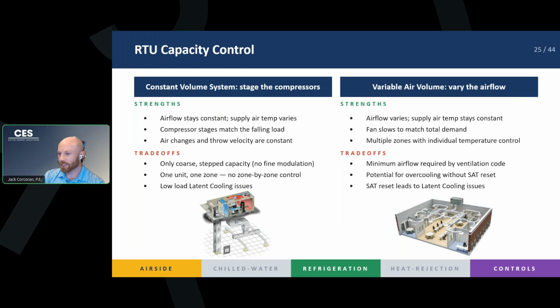The drawbacks of this is that, I will say many modern rooftop units can use variable speed compressors that can modulate just like VRF, and those are very powerful, but they add to the cost, and maybe you don't need it. So the simple rooftop configuration, constant volume with staged compressors, has some trade-offs that you can imagine. You can only step the capacity, right? What if you wanted somewhere in between high and low heat or high and low cooling? You're either going to be overcooling it or undercooling it, depending on if you pick the high or the low mode to be in.